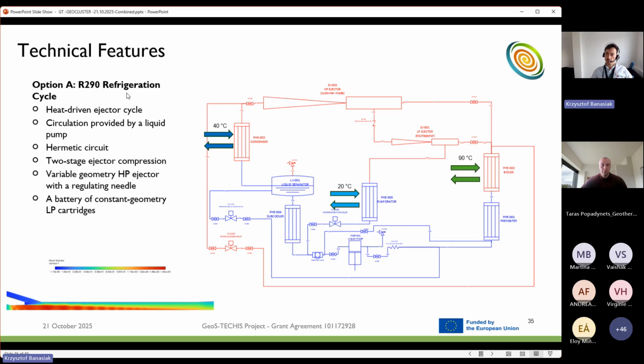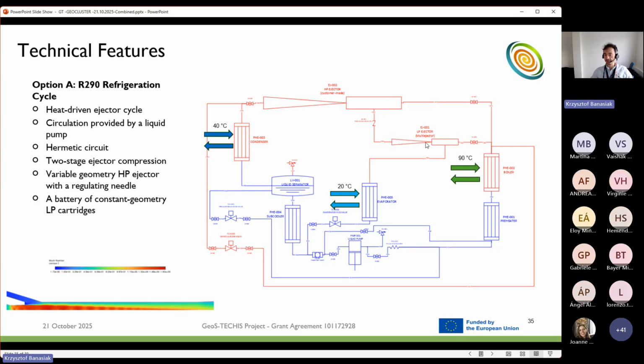In the end it's a propane refrigeration cycle, heat-driven, supported by ejectors, a pump, and 2 ejectors. Why 2 ejectors? Because for the given conditions, with 90 degrees Celsius geothermal water, producing 20 degrees Celsius utility, and ambient conditions around 40 degrees Celsius, there's no way the whole cycle could run with only 1 compression stage in the ejector. We need 2 stages of compression, meaning the ejectors are connected in series.